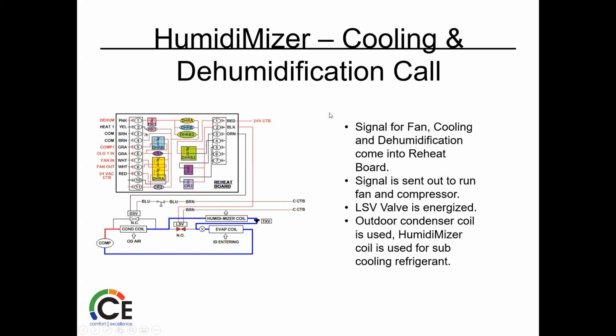And it happens. And again, at this point, unless there's some weird thing, which our standard guys, if any of the standard guys are here, we know we had a little issue with a low ambient control that was keeping the fans from ramping up, and we weren't dehumidifying right, and we were blowing a compressor. So there's some hitches with everything, but when everything is right, this thing will run at the same time, and you'll get great operation for your customer.